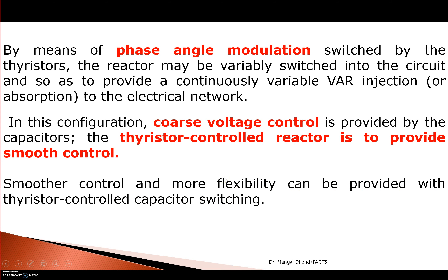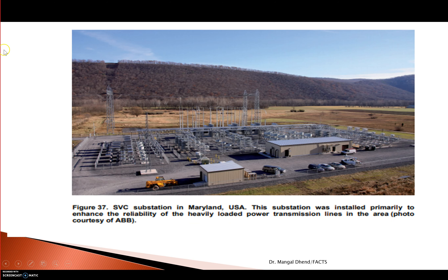This is similar to TCR-FC, but here it is more advantageous because in the last session we saw that TCR-FC requires a higher TCR rating, produces larger harmonics, and requires a larger filter size. This picture shows an SVC installed in Maryland, USA, installed by ABB.